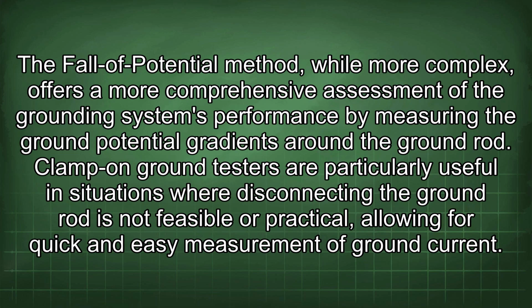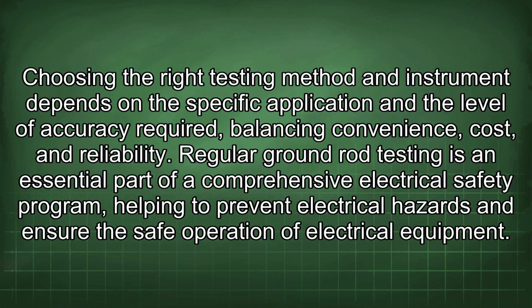The fall of potential method, while more complex, offers a more comprehensive assessment of the grounding system's performance by measuring the ground potential gradients around the ground rod. Clamp-on ground testers are particularly useful in situations where disconnecting the ground rod is not feasible or practical, allowing for quick and easy measurement of ground current. Choosing the right testing method and instrument depends on the specific application and the level of accuracy required, balancing convenience, cost, and reliability. Regular ground rod testing is an essential part of a comprehensive electrical safety program, helping to prevent electrical hazards and ensure the safe operation of electrical equipment.